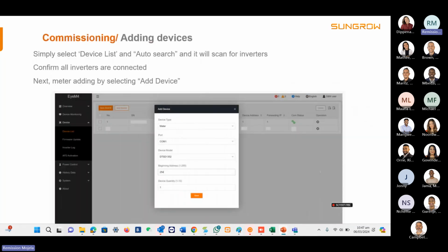Then we have adding the devices. So when we add the devices, normally the device that we add is the meter, like I was saying. The Sungrow devices will be automatically picked up by the logger, and then you just have to add the meter. You just have to select the type of meter, the port that it is connected to, and whether it's a gateway or an electricity meter, but the standard Modbus address for the DTSD1352 is 254. That's the standard Modbus address to communicate with Sungrow devices.